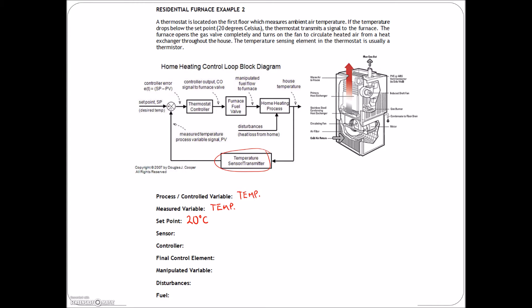The thermostat is quite small — it's basically just a solid-state chip that's looking at that input, and mounted on that chip is a thermistor. The thermistor basically changes resistance as the temperature changes in the room. The controller for this system is the thermostat. The final control element — well that's what we're turning on, and there are three things we can turn on: a valve, a motor, or a heater.